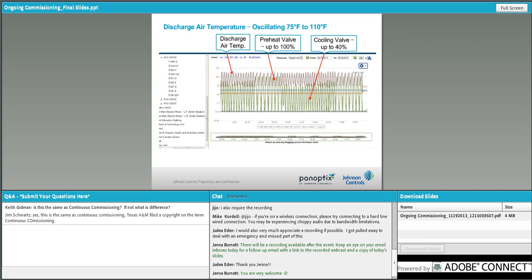This example is a discharge air temperature. We can see that this is in heating mode, obviously. The air temperature is oscillating between 75 and 110 degrees. The preheat valve is up to 100%, and the cooling valve is having to come up to 40%. This is out of tune. It's just fighting back and forth. You can see the heating and cooling are in constant combat trying to control this set point. It really looks like it's just out of tune and needs to be retuned.